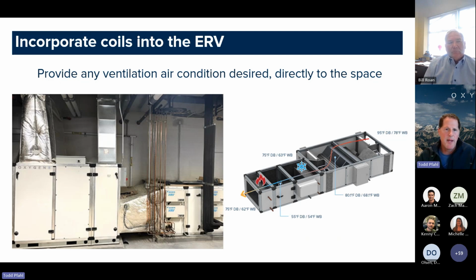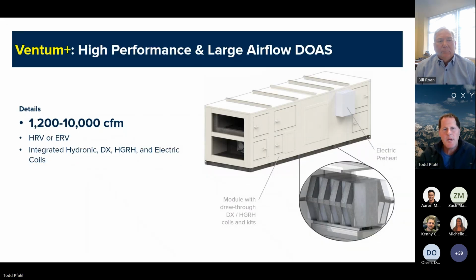Everything you see there is a factory package. Even the stuff you can't see there is factory packaged at our factory. So the controllers that control the Daikin electronic expansion valves get mounted at the factory and wired. The electronic expansion valves are factory mounted, brazed to the coil and wired. And then all of that gets connected back to our DDC controller. So we have a very simple, quick installation for the contractor. They just have to bring power to it and connect up their piping to the rest of the VRV system. So very simple solution.